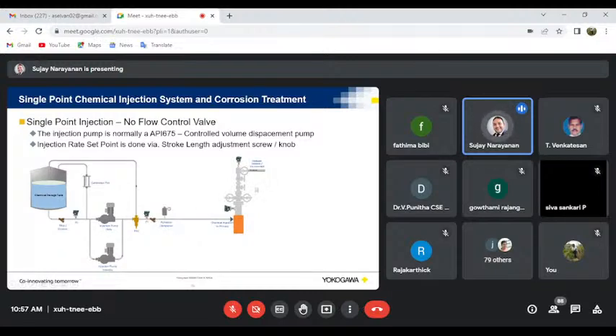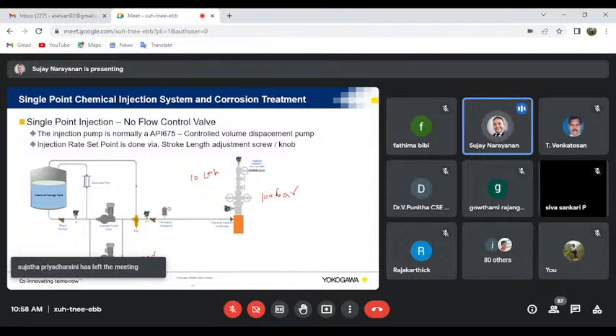So now let's say this well is at 100 bar. Sorry, my handwriting is bad, especially on a mouse. This well is at 100 bar pressure, and now if you want, let's say, a 10 liters per hour injection rate, this pump should be operating at least at 110 bar. So the delta P should be at least 10 bar. Of course, it is Bernoulli's principle: the higher the delta P, the higher the flow rate. So that's how it operates.